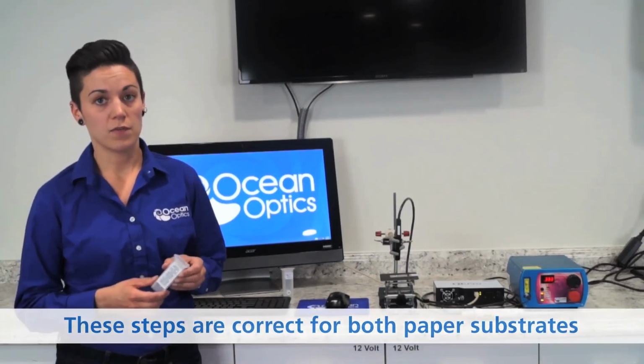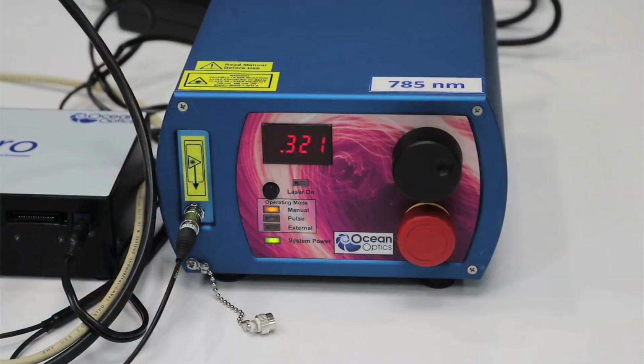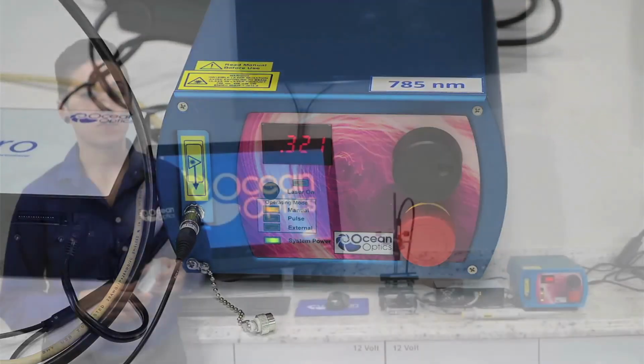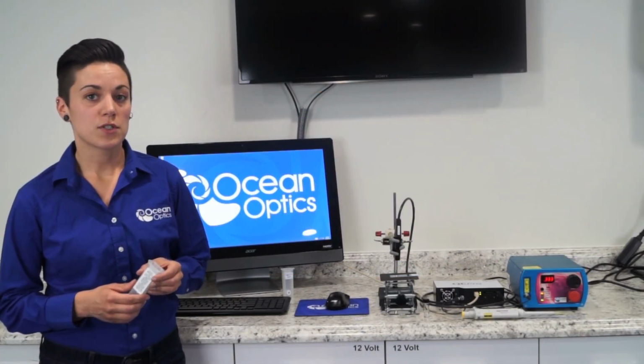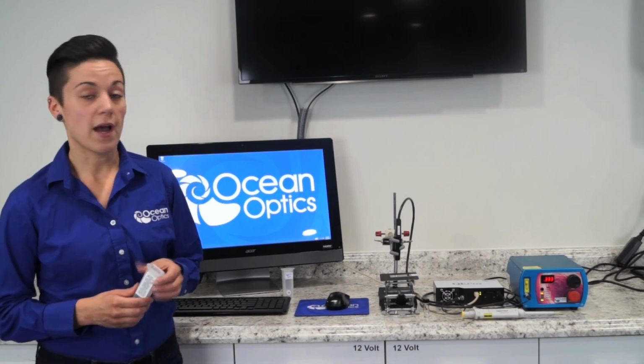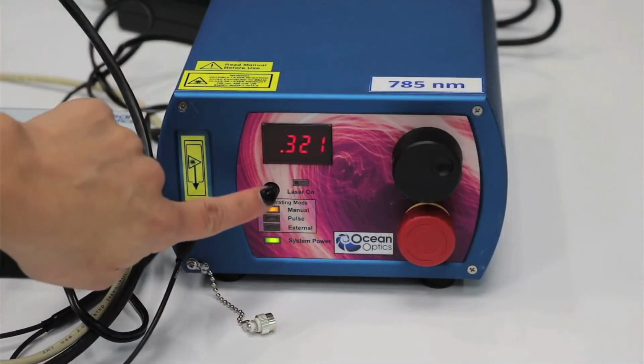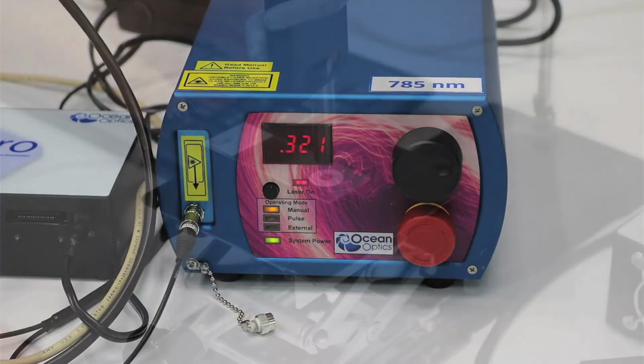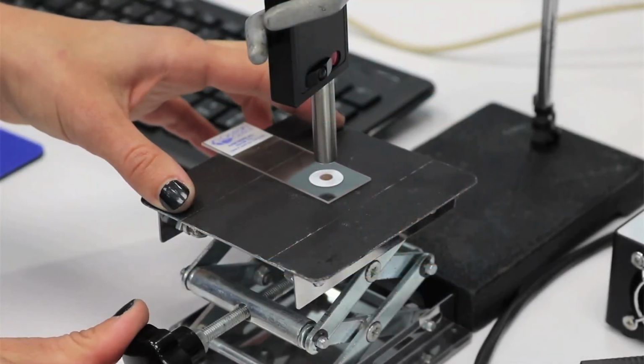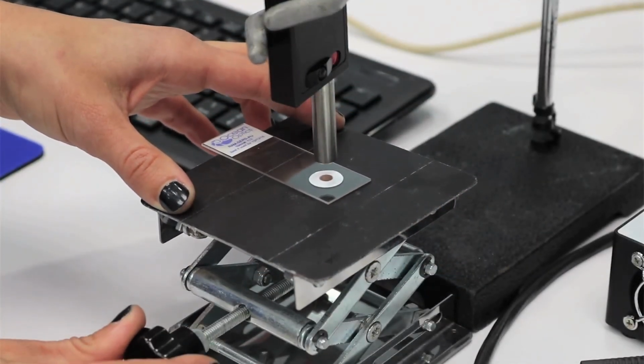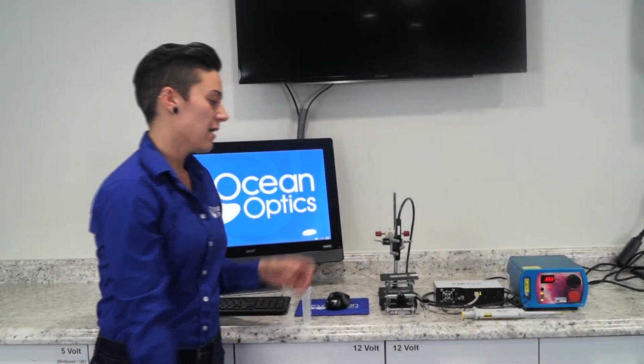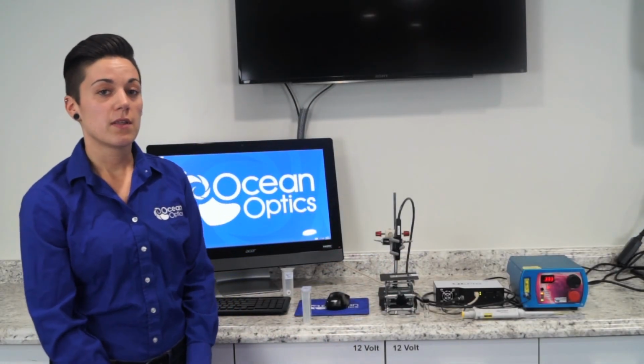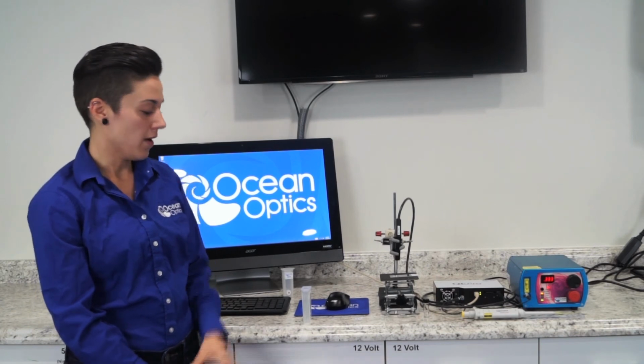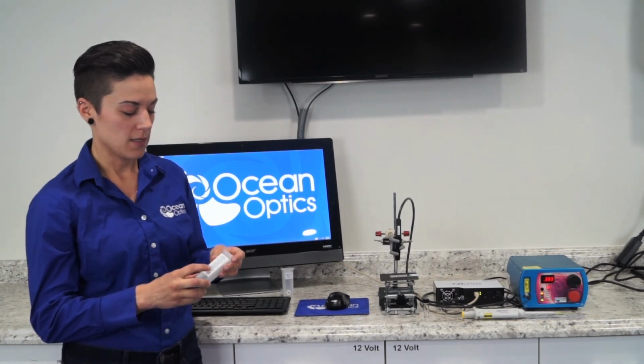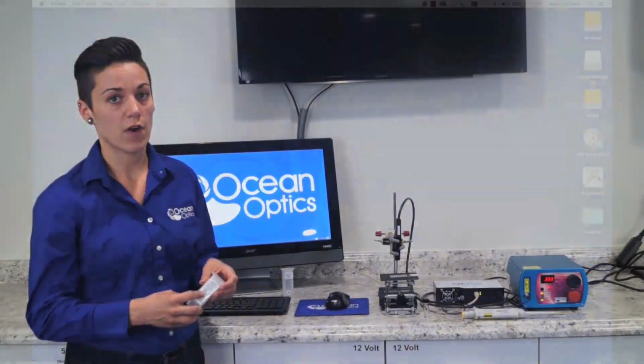The first step involves focusing the laser. The laser power is set to 15 milliwatts for the gold or silver paper substrates. This ensures that we do not burn the substrates with higher laser powers. We're going to turn the laser on, and then we're going to focus the laser spot on the substrate by adjusting the stage up or down. Once we see that the laser spot is focused, we're going to then follow the next step on the package, which is taking a dark reference of our sample.